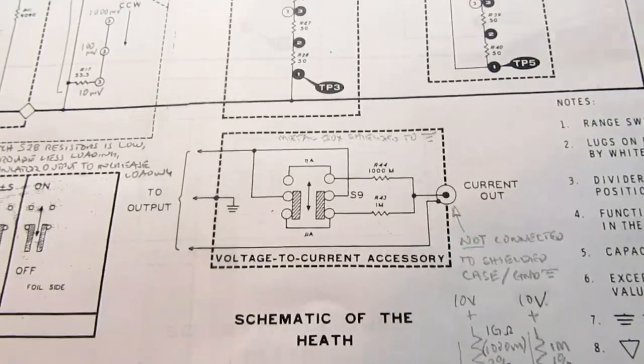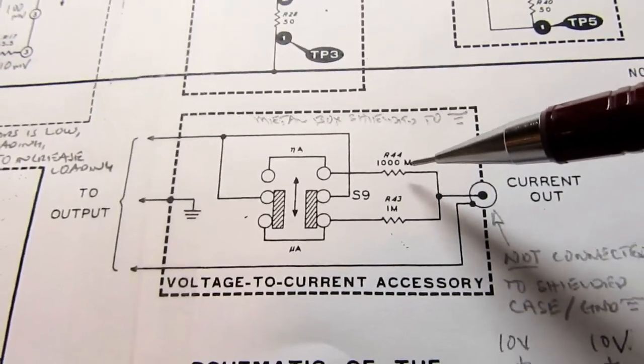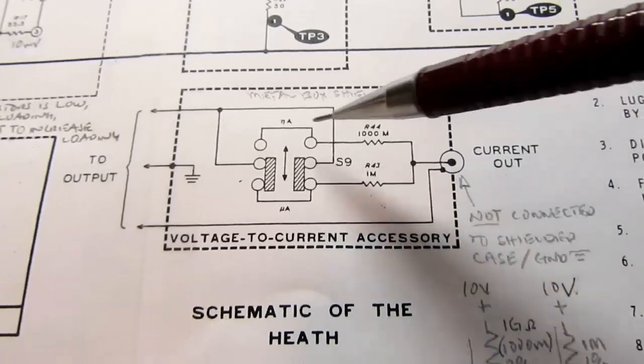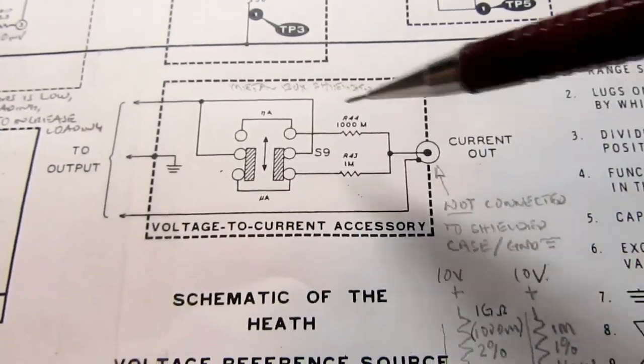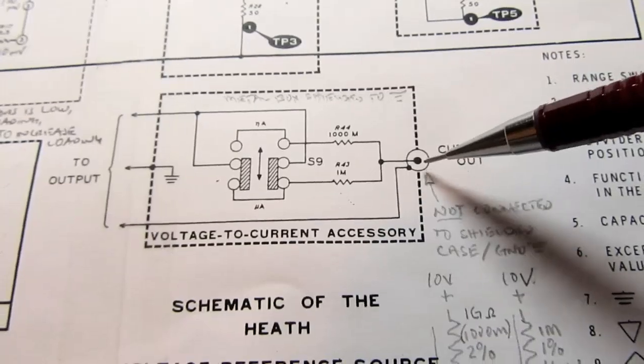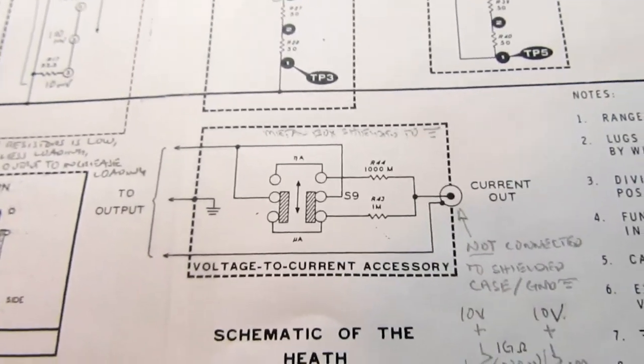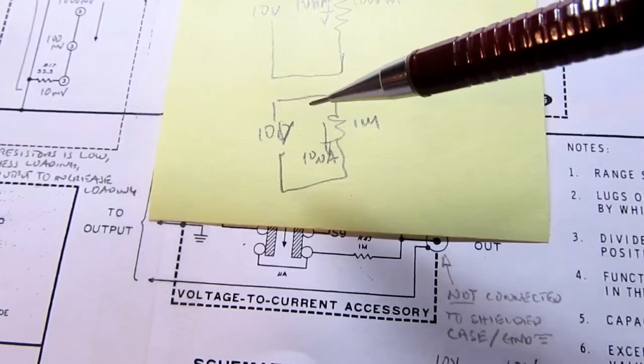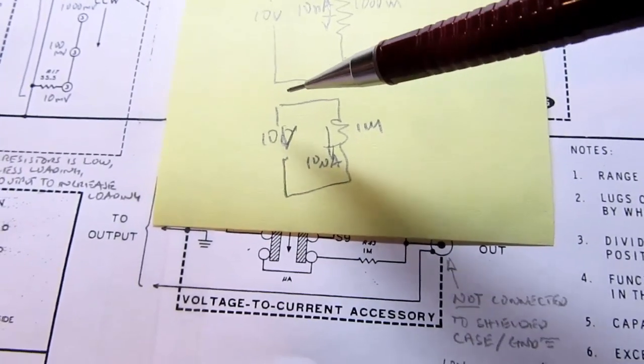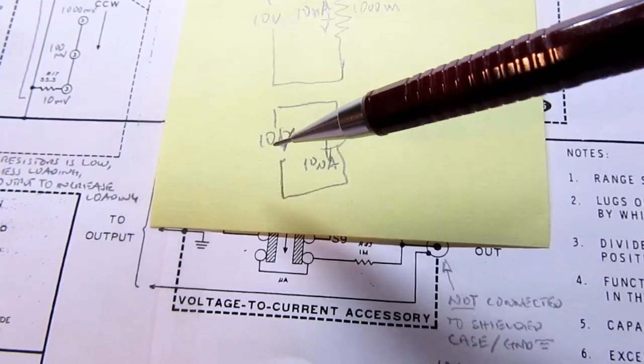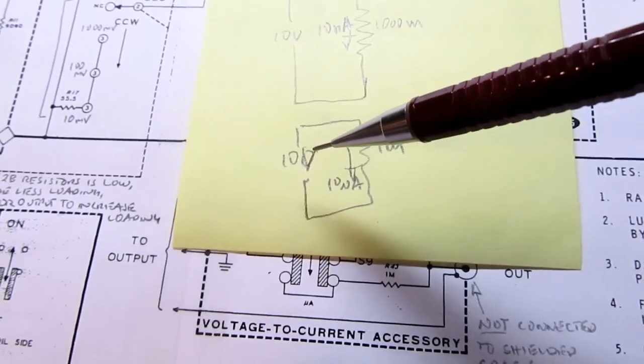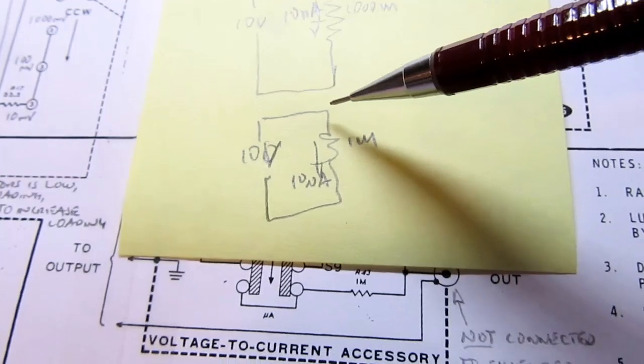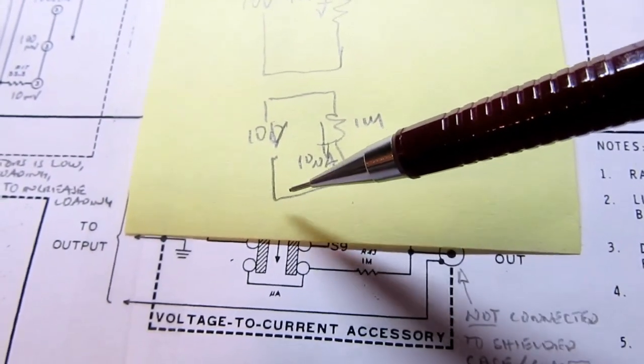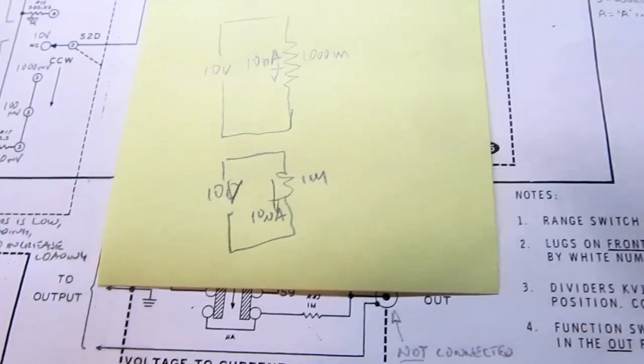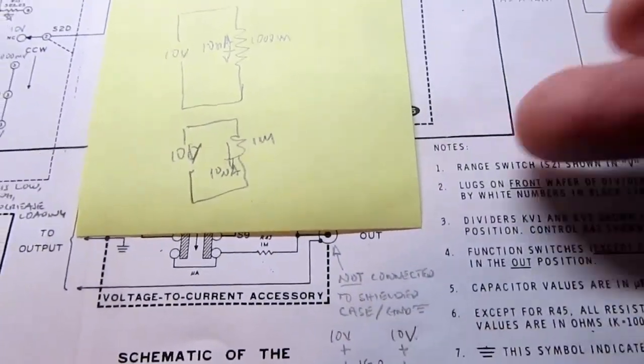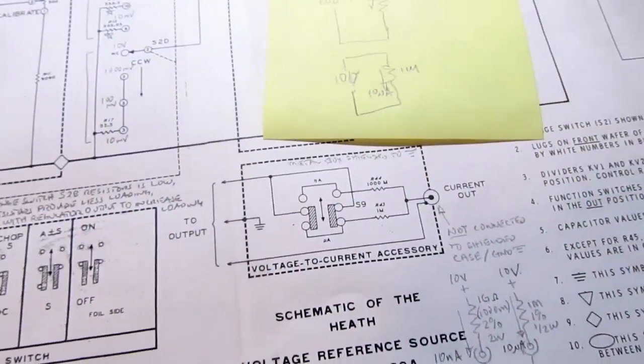It keeps it isolated. So you're either adding a 1000 mega ohm resistor in series with the output on the way out of the voltage reference source, or you're putting a 1 meg resistor in there. To use this accessory, you're supposed to use the voltage reference source in its highest range, which is the 10 volt range, assuming it's set to 10 volts, and then you're essentially putting a 1 meg resistor across that, because it's presumed that whatever you have tied to the output is some meter movement.